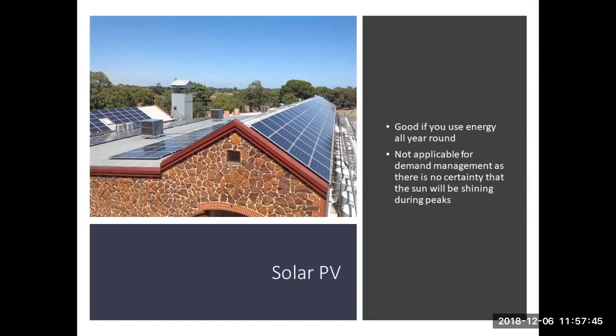But solar generally aims at improving your on-site energy consumption. You can't really count on solar being used as a demand management strategy because you don't know the sun's going to be shining. So we can't say, okay, when we're reaching our peak in demand in the afternoon, our solar system is going to drop that by say 30 kilowatts if it's a 30 kilowatt solar system, because you simply don't know that it's going to be producing that much power. So while solar can be a good investment, it's not really applicable for demand management.